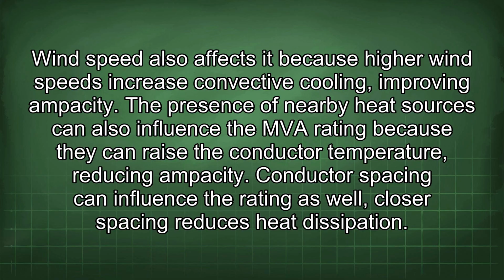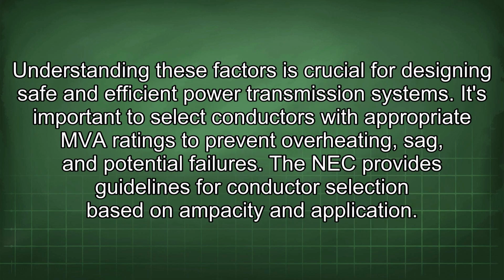The presence of nearby heat sources can also influence the MVA rating because they can raise the conductor temperature, reducing ampacity. Conductor spacing can influence the rating as well. Closer spacing reduces heat dissipation. Understanding these factors is crucial for designing safer and efficient power transmission systems. It's important to select conductors with appropriate MVA ratings to prevent overheating, sag, and potential failures.